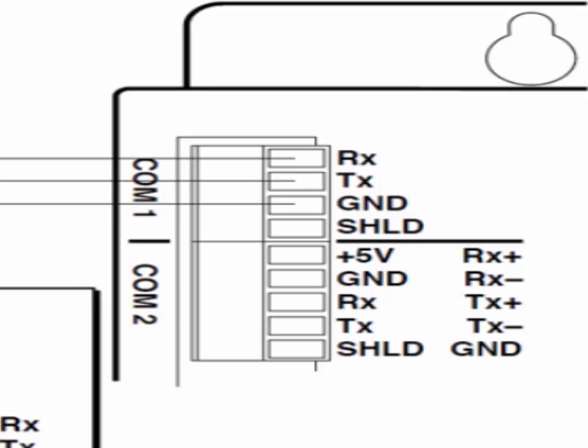On the Zeta 6000, a DIP switch internal to it can change it to RS-485 communications. If there's anything connected to COM-2, go ahead and disconnect that device. You can just pull the connector out. That way, anything trying to communicate to the Zeta 6000 is not going to try to interrupt the communications that we're going to try to establish on COM-1.